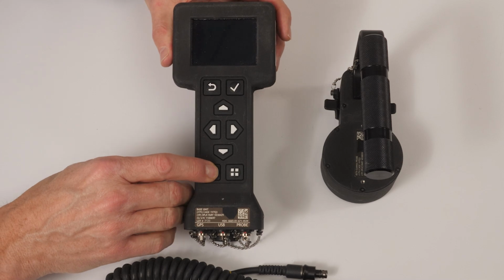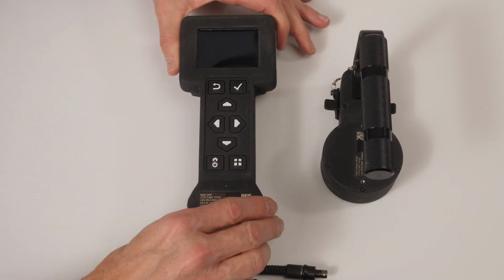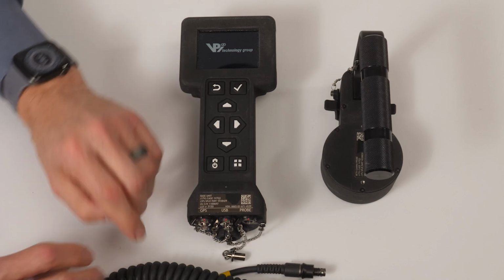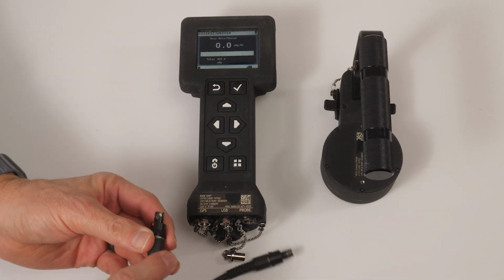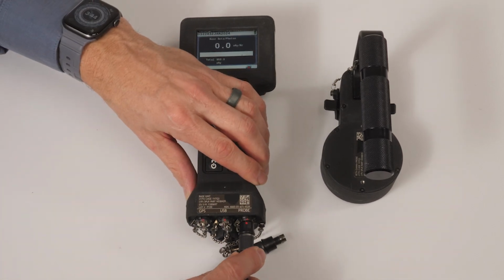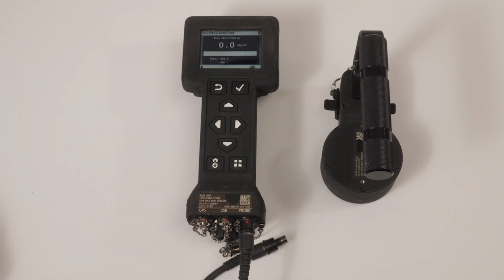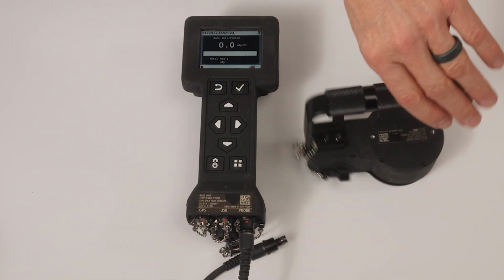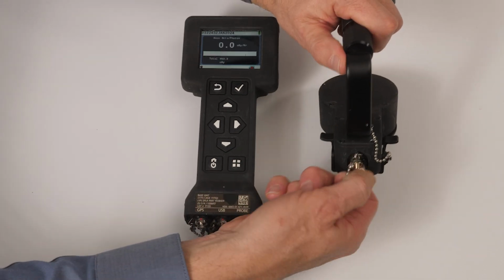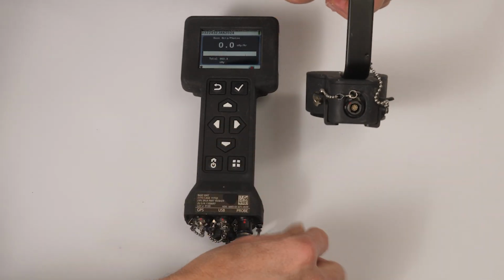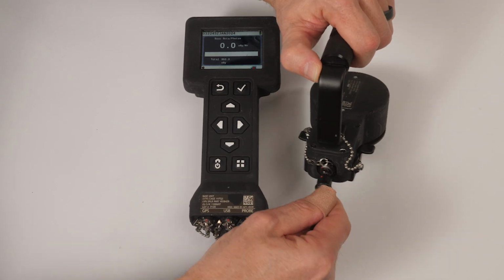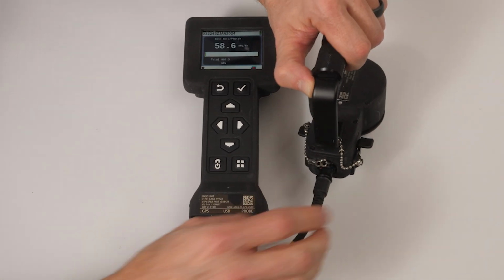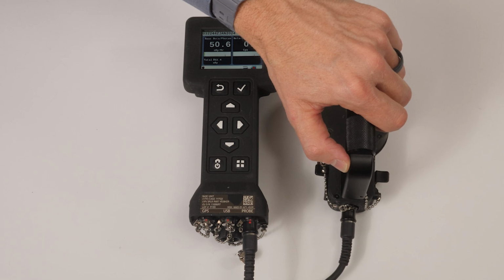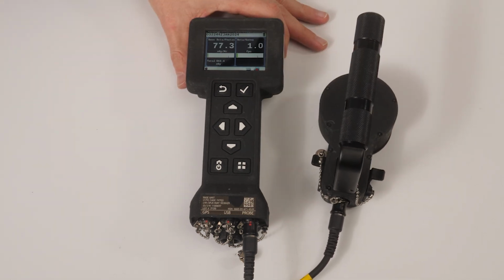To place the small area beta gamma probe in operation, first ensure that the base unit is powered on. Remove the probe connector protective cap from the base unit and connect the common probe cable to the base unit probe connector by aligning the red dot on the base unit connector to the red dot on the end of the common probe cable collar. Insert until an audible click is heard. Remove the protective cap from the probe and connect the other end of the common probe cable by aligning the red dot on the probe to the red dot on the end of the common probe cable collar.